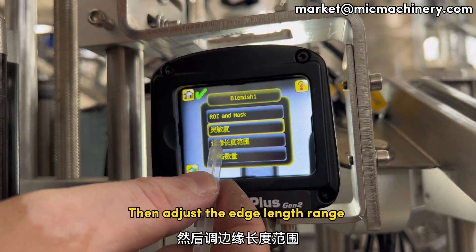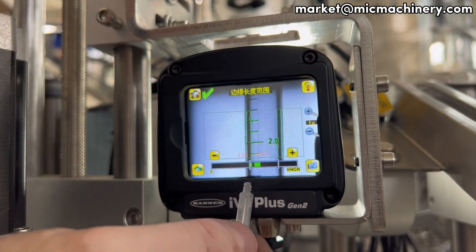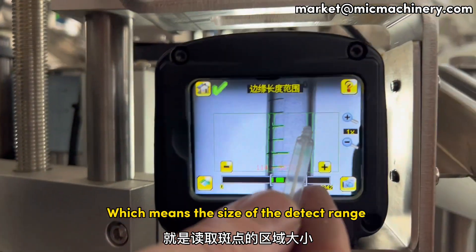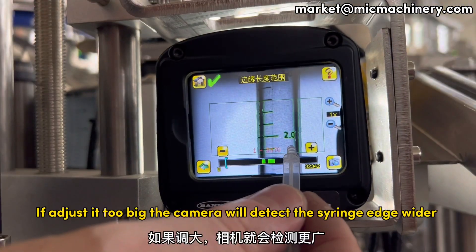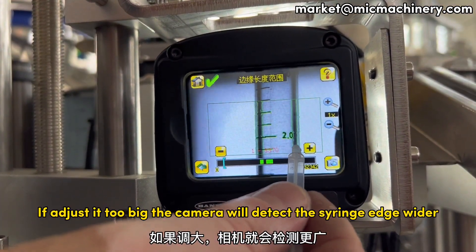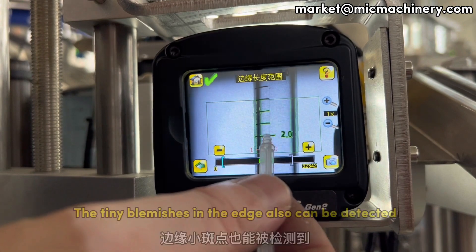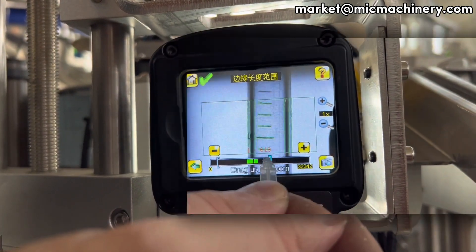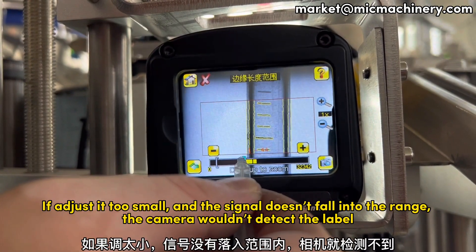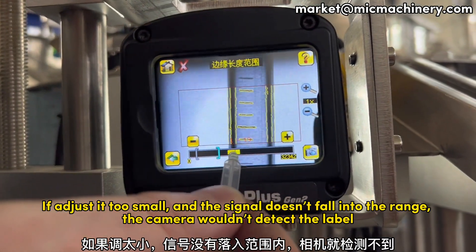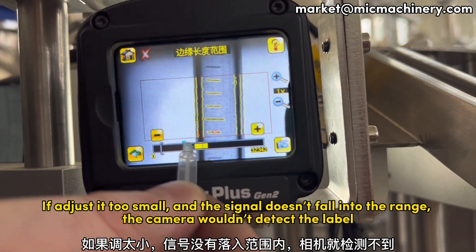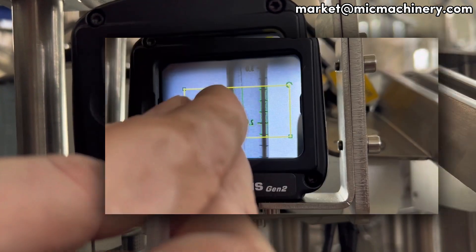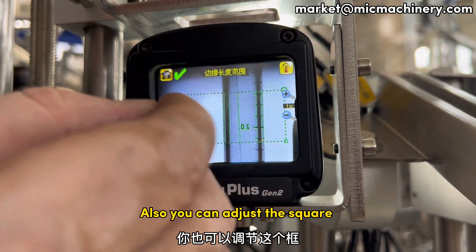Then adjust the edge length range, which defines the size of the detect range. If adjusted too big, the camera will detect the syringe edge wider, and tiny blemishes at the edge can also be detected. If adjusted too small and the signal doesn't fall into the range, the camera won't detect the label. Ensure the signal is within the range. You can also adjust the detect rectangle square.